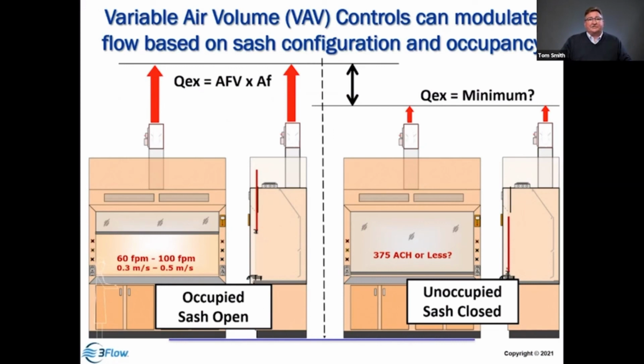So when the sash is open, we've talked about this now several times, the face velocity multiplied by the area of the opening equals the exhaust flow. But when that sash is closed, there is no sash opening. You can't measure face velocity. So how do we know we have adequate flow, and how, and who, sets that minimum flow? How do we know it's appropriate?